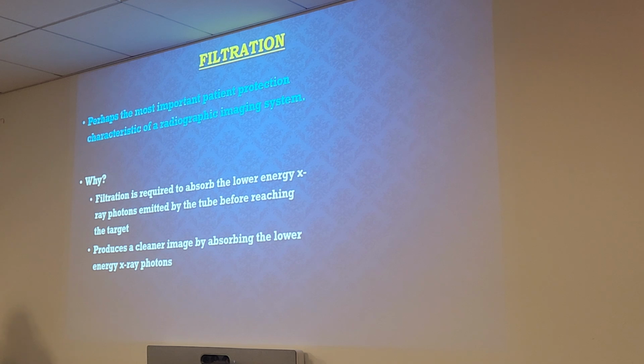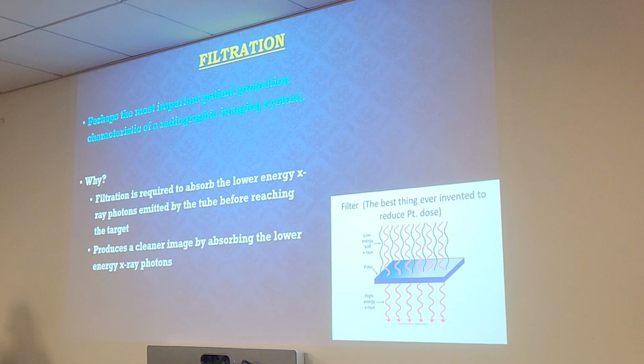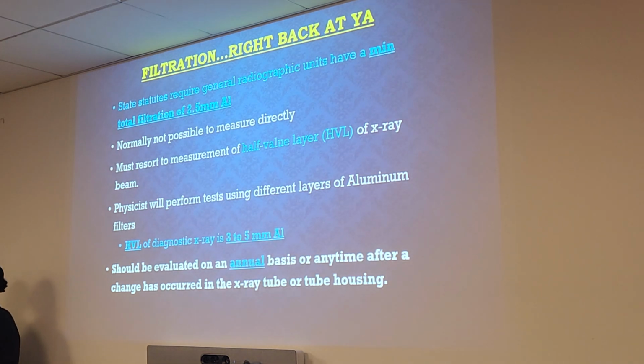Low energy X-rays. Yes, so filtration is there in place to filter out the low energy X-rays, and it's to clean up your image. Clean up that scatter, clean up the noise on your image. Okay? So most states, if not all states, require at least 2.5 millimeters of aluminum for total filtration.